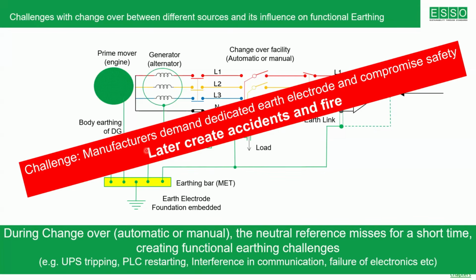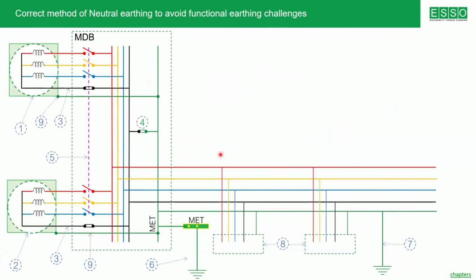Now, to avoid that particular problem, the manufacturer is demanding to make a non-standard electrical installation earthing system, and this non-standard earthing system is going to create a fire and accident in your building. Of course, the best method is, don't make a non-standard method. Now, in the same standard, starting from 1987 IS 3043, alternate methods of earthing are being explained.